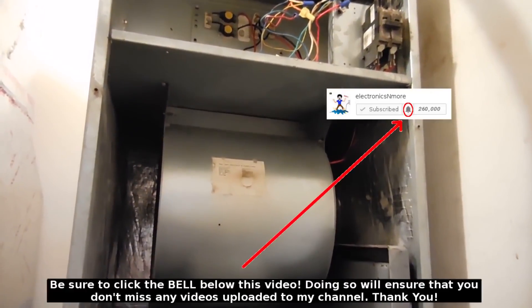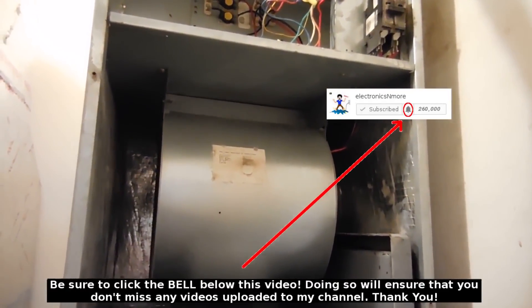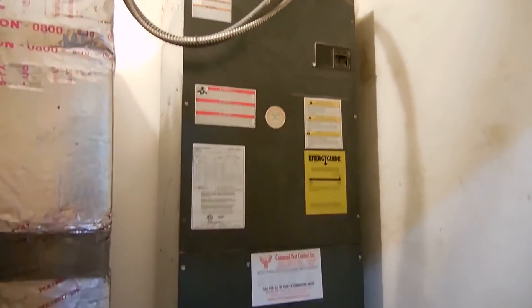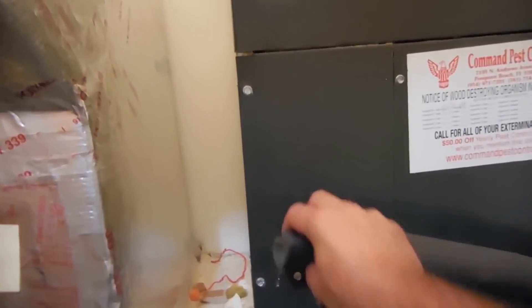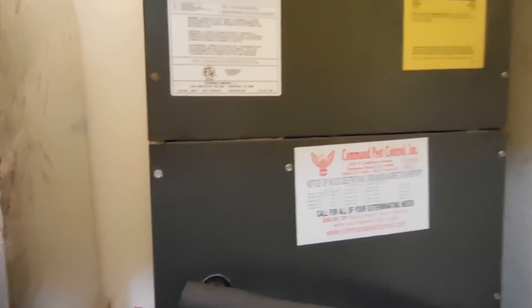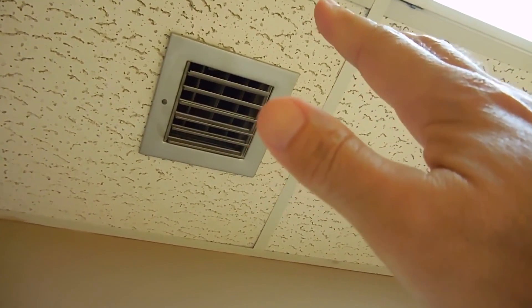The air conditioning system was working just fine before — cycling on and off, good cooling — so I shouldn't have to check the refrigerant. The system is up and running and it's nice and quiet now. You can see there's no more freezing on the suction line, just cold. Let's go feel the vents — air coming out nice and cold.